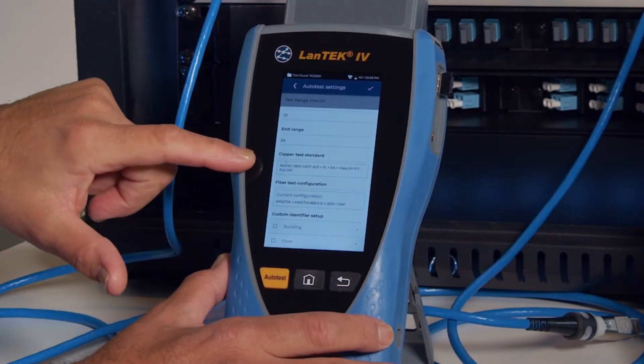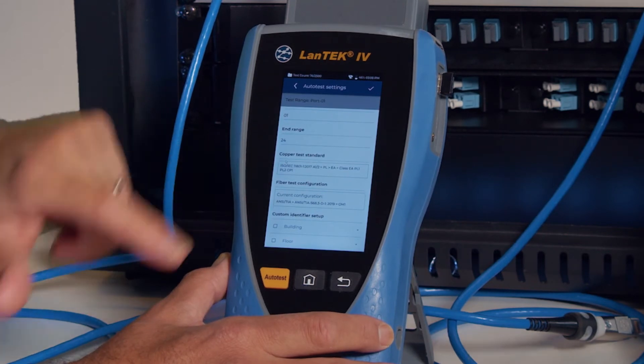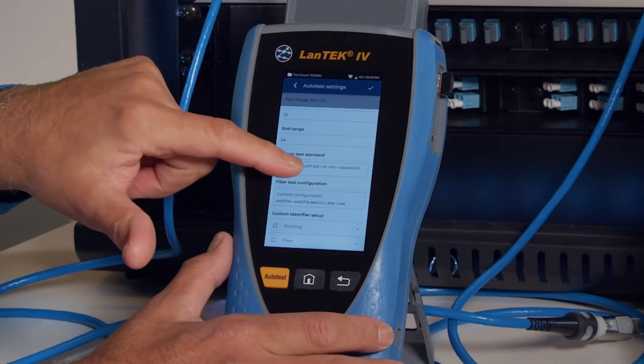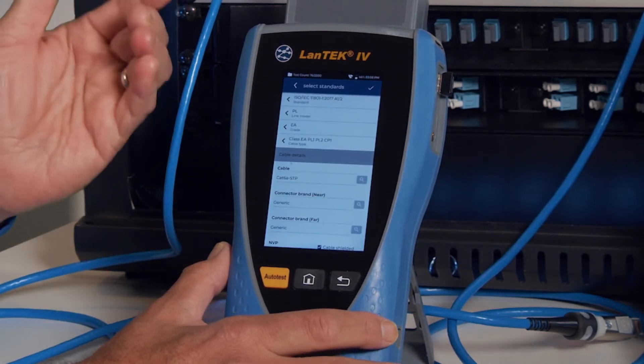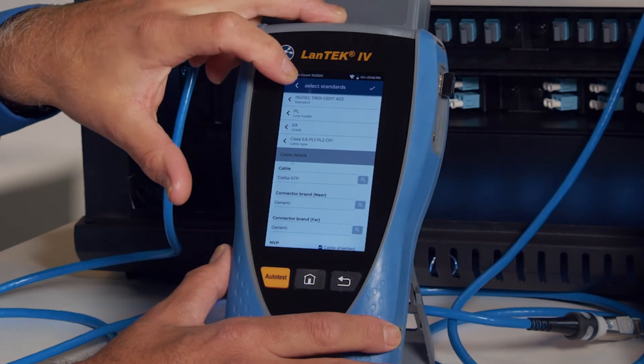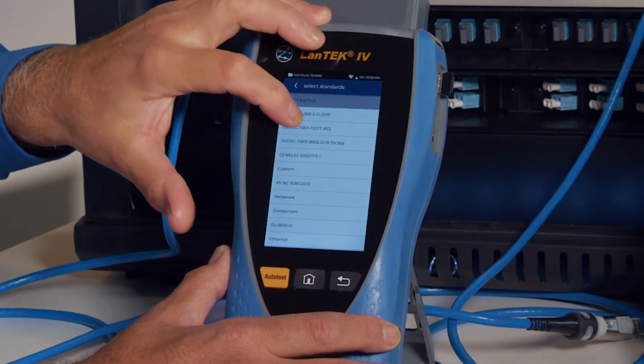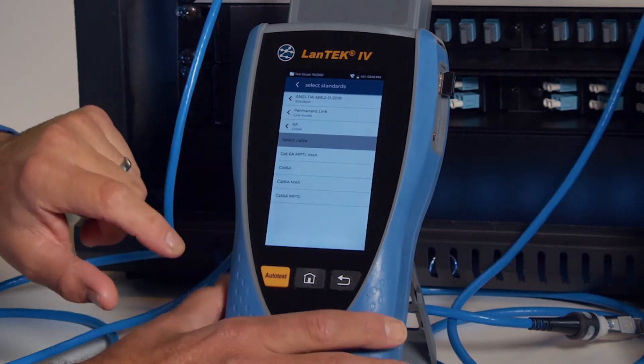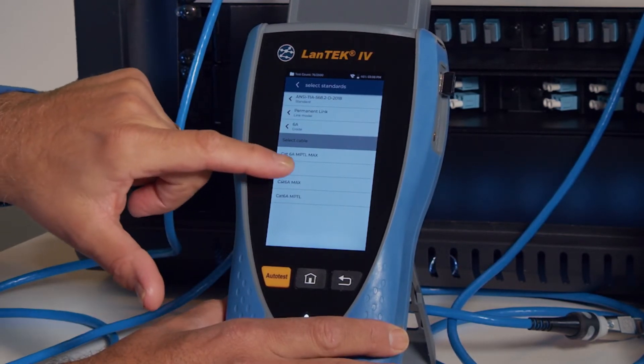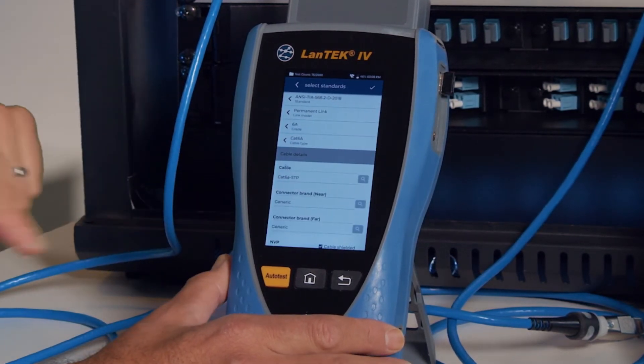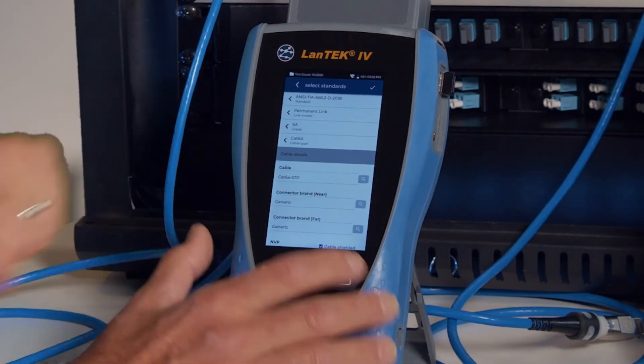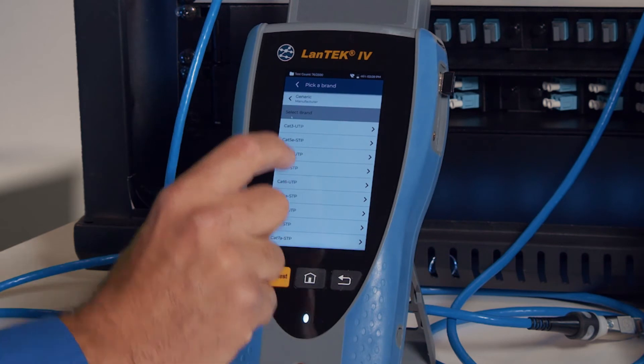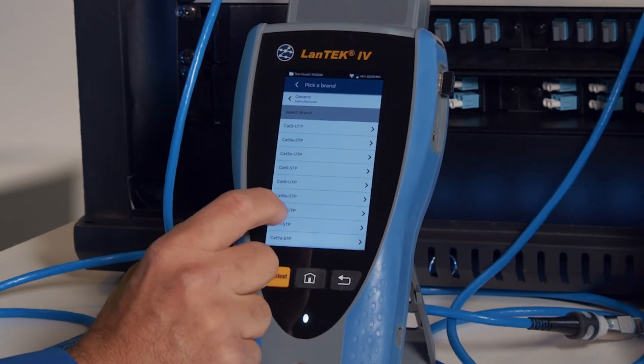Probably most importantly would be your test standard. Currently this tester is set to default to ISO Class EA. But maybe I want to default to TIA CAT 6A, for example. So I will change it from ISO to TIA permanent link CAT 6A, and instead of CAT 6A max, we'll just do the regular CAT 6A. And we want to use UTP cabling, so I'll go generic CAT 6A UTP.